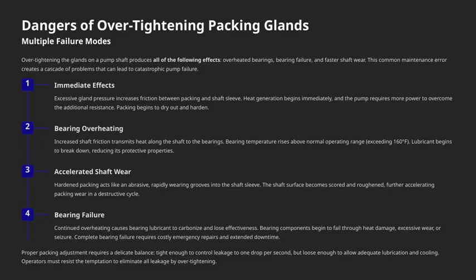Let's talk about the dangers of over-tightening packing glands. When you tighten the glands too much on a pump shaft, it can trigger several failure modes that seriously impact the pump's performance and lifespan. One of the first issues is that it causes overheated bearings and can even lead to bearing failure, which then accelerates shaft wear. This small mistake in maintenance can set off a chain reaction resulting in catastrophic pump failure.